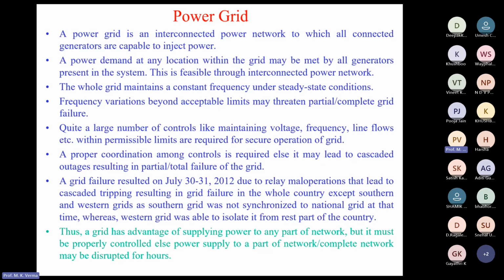Apart from frequency control, it requires quite a large number of other controls, like maintaining voltage, keeping line flows within limits, controlling reactive power flows, keeping losses to a minimum, and improving the voltage profile in the best possible manner. Now, once we have an interconnected system, a lot of controls are required to maintain its proper functioning. So there must be proper coordination among controls. Otherwise, instead of helping the grid, improper control may lead to outages, and it may even result in cascaded outages, resulting in failure of the grid.